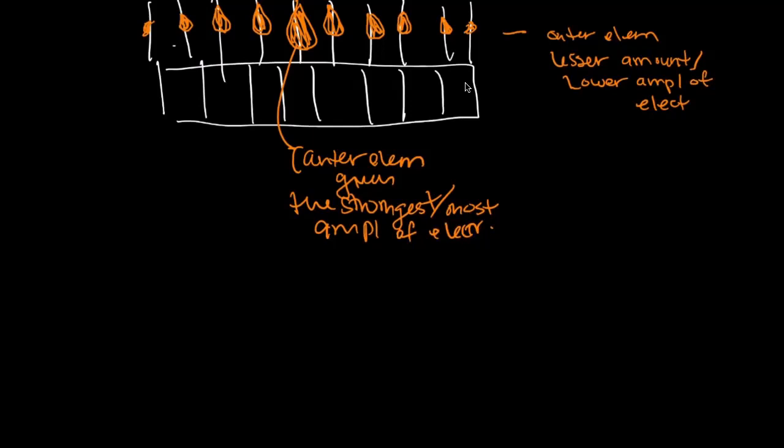So that's not the main idea. A lot of times when I ask students about apodization, they tell me, oh, elements are given electricity using time delays. No, that's phasing. Yes, time delays are still being used here, but the whole purpose of apodization is to understand that there's a different amount of electricity, more in the center, less at the outside.